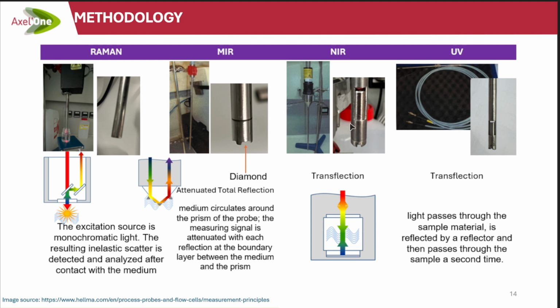If you use NIR, you will be working with a transreflection system, because in this case you can go through a much thicker part of your product. The optical path can be much bigger, so the light goes forward. There's a mirror at the bottom where you can adjust the path length you want to be measuring in your product, and the signal you get is called transreflection. So it's transmission, but with a bit of reflection signal in it.